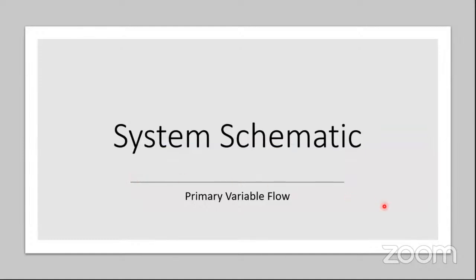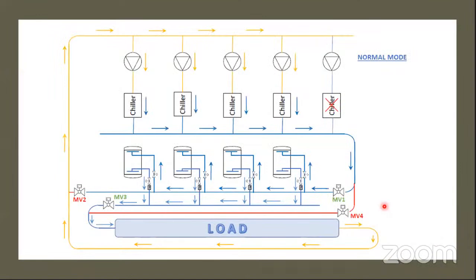Now we will see what the system schematic is with a primary variable flow pumping system. Here you see there is only one pumping system, that is primary variable, the chiller, and we have thermal storage tanks also. So it's in normal mode.